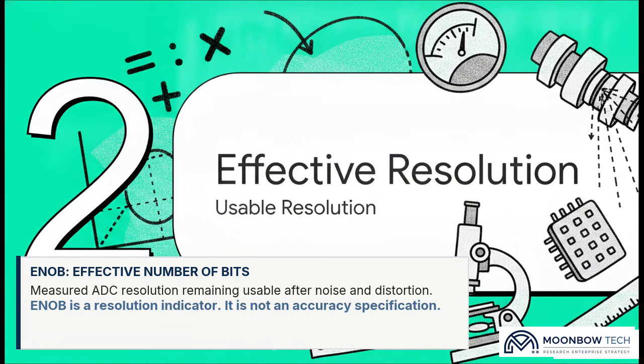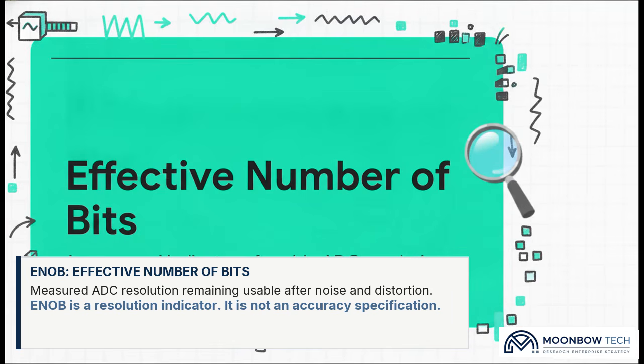Moving on to step 2. Effective resolution. To face reality, we have to talk about ENOB, or the effective number of bits. This is a measured indicator of the ADC resolution that actually remains usable after the instrument's own internal noise and distortion take their toll. I literally cannot stress this enough. ENOB drastically reduces your usable resolution, but it is still not an accuracy specification.